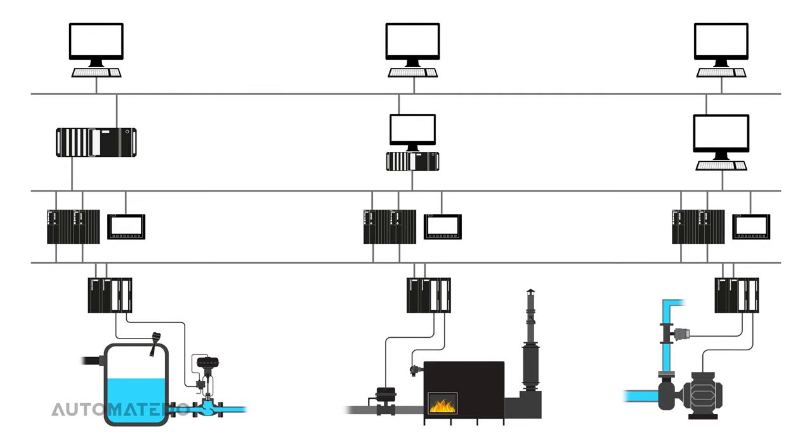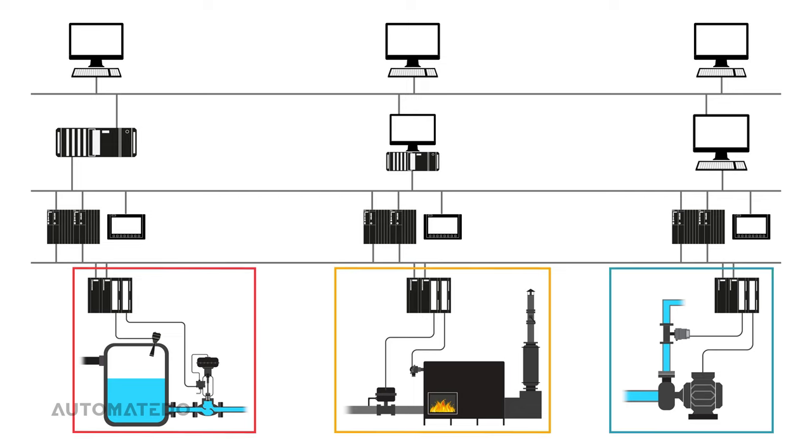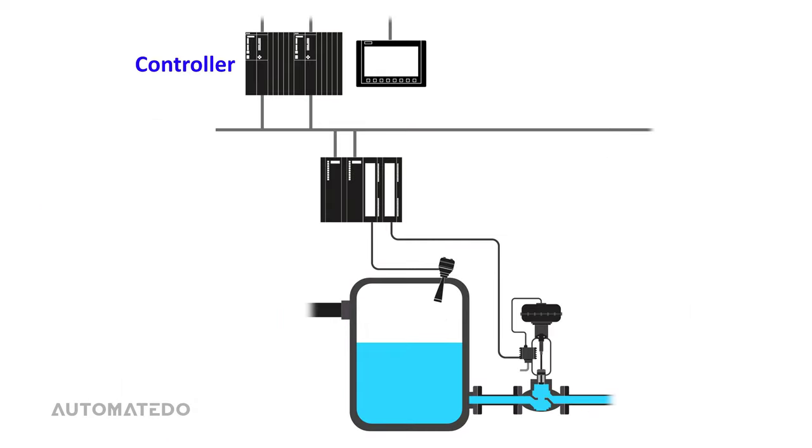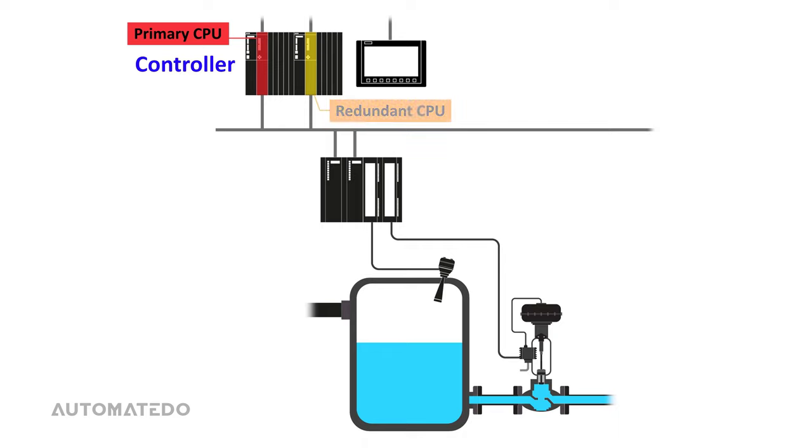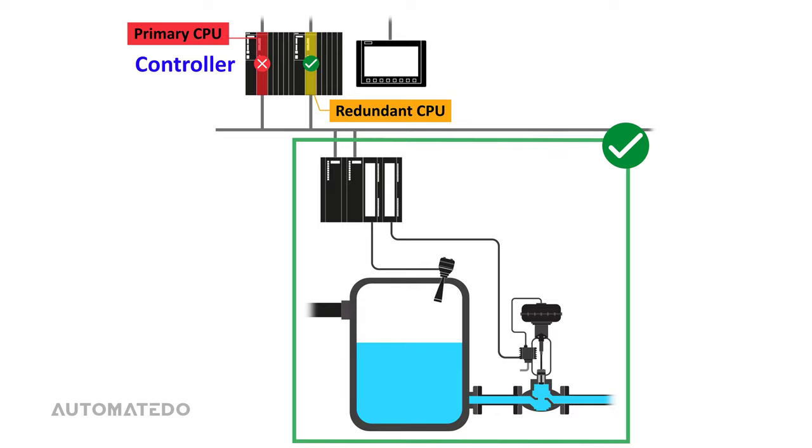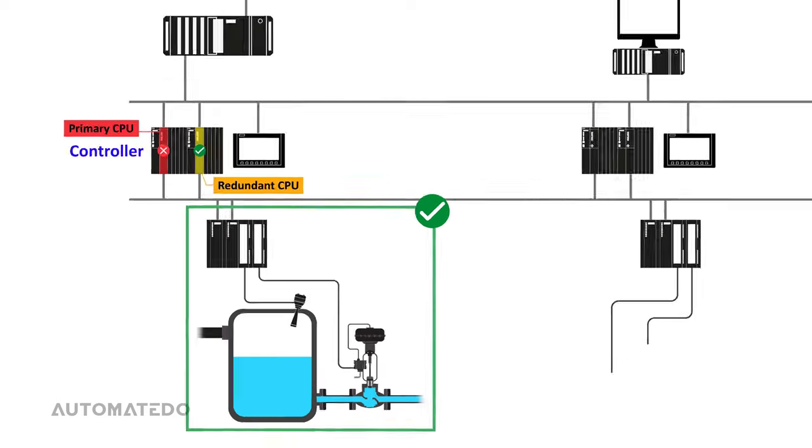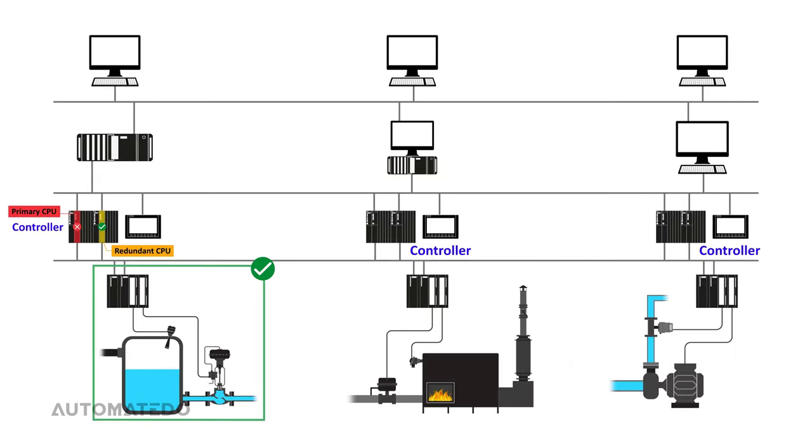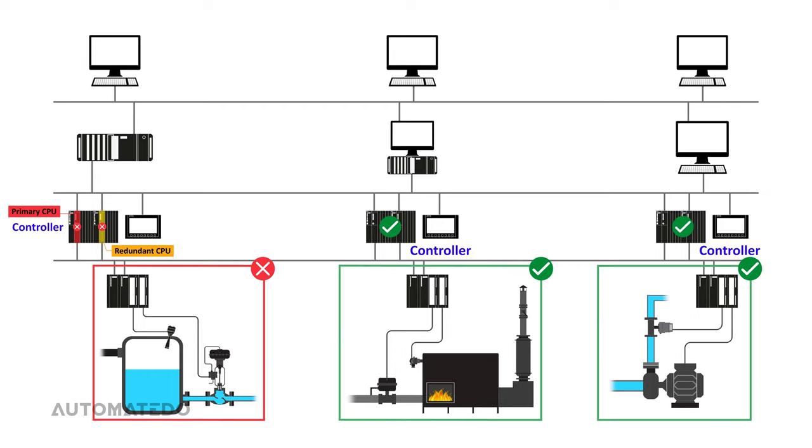Now let's discuss the DCS features in the last segment of this video. Each section of a DCS system has its own dedicated controller that works autonomously. There would be two CPUs instead of one in a DCS control cabinet. One is our primary CPU while the other is a redundant CPU. If the main CPU fails for whatever reason, we have a redundant CPU to take over. If in a scenario the redundant CPU fails as well, only that section of the plant's operation would be affected, and the rest of the areas will continue to operate without interruption.